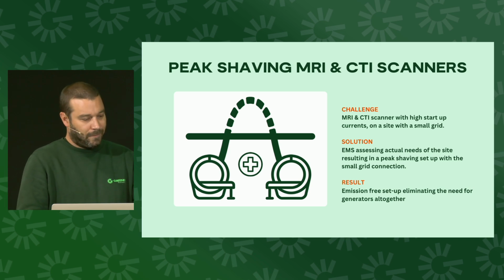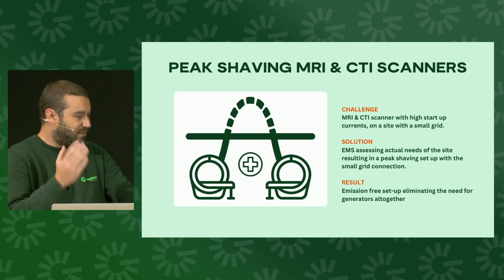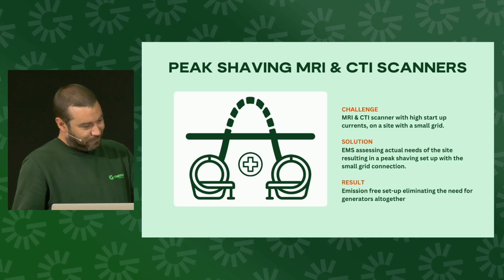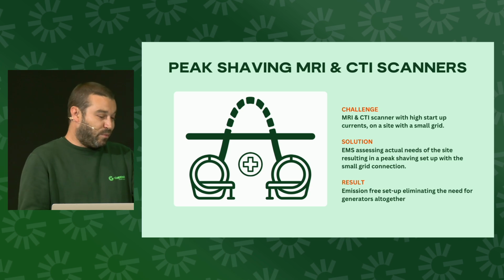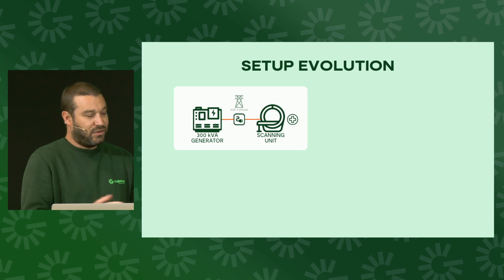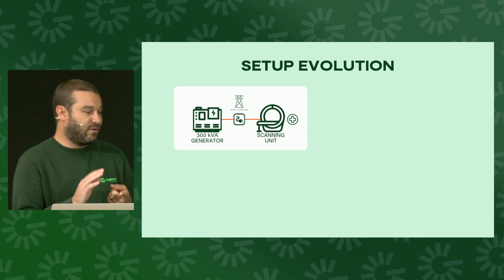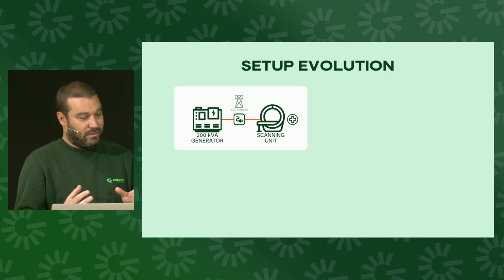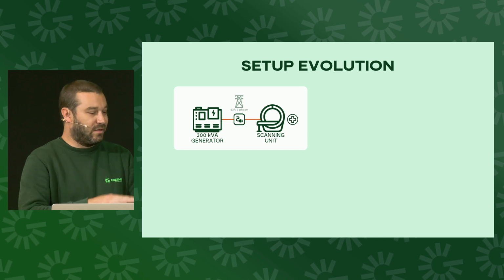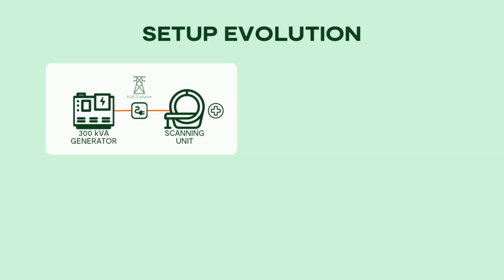Old school star delta motor startups, 100%. So we were approached with a problem. The initial setup on site was one individual scanner. The technical sheet for the scanner suggested inrush currents could be around 300 amps, so a 300 kVA diesel generator was specified to power it. But there was also a 63 amp three-phase grid connection on the site, which you can see here.